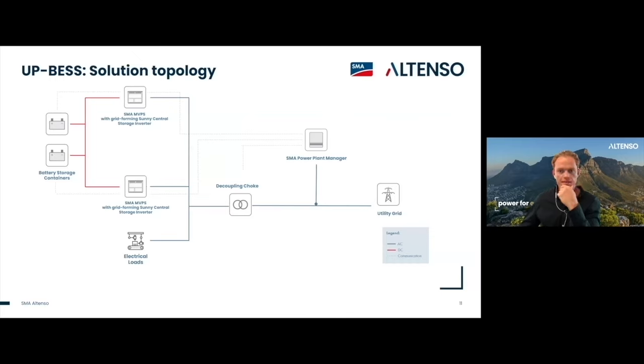So here's a basic schematic of how the typical system would work. Generally, there would be 2 MVPSs converting DC power from the batteries to AC and connecting on the AC bus. And the system would essentially run in parallel with the load. And this would contrast your typical inline UPS or double conversion system, which is sometimes used to provide uninterrupted power supply to critical industrial loads. The benefit of this solution is that you're able to provide uninterrupted power to your whole load. So the solution essentially acts as a power stabilizer and not just a power conditioner.